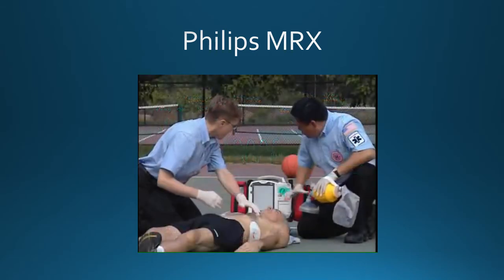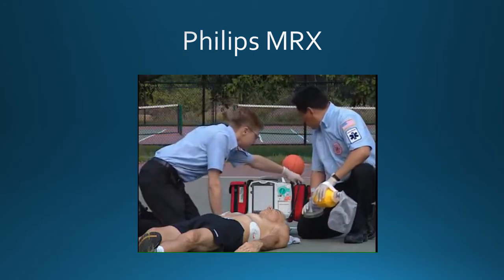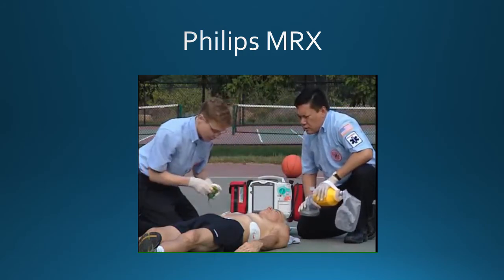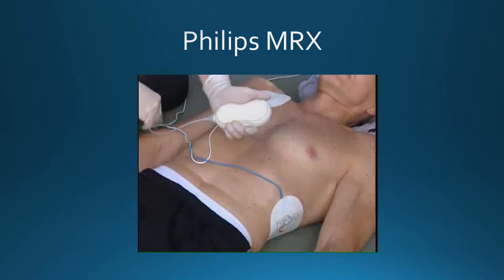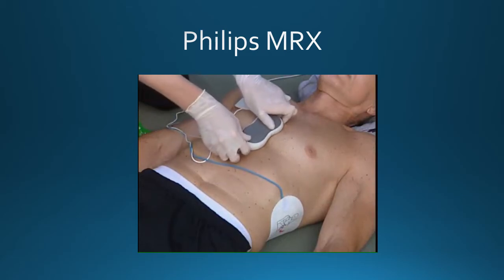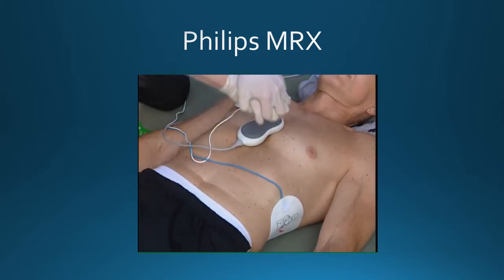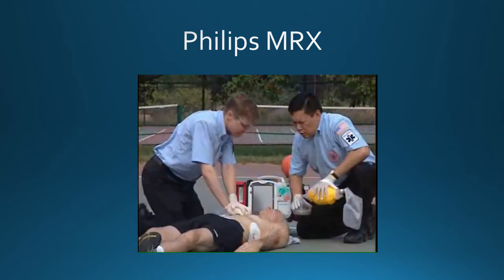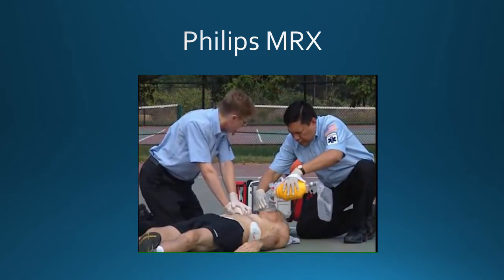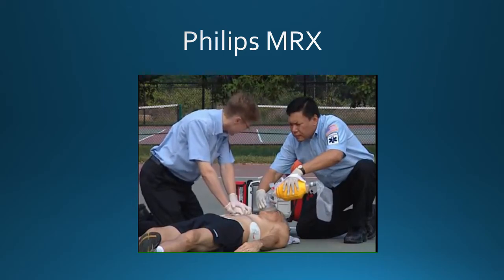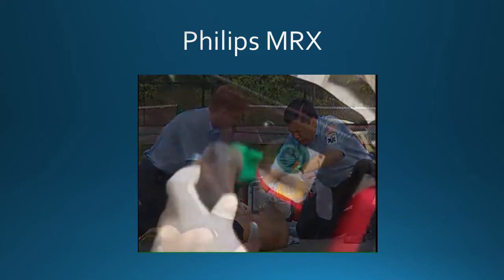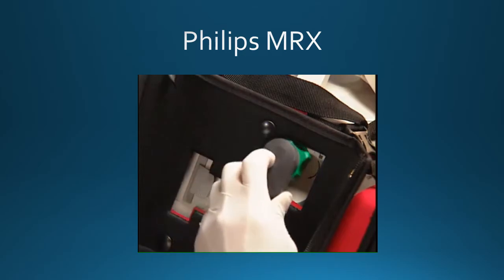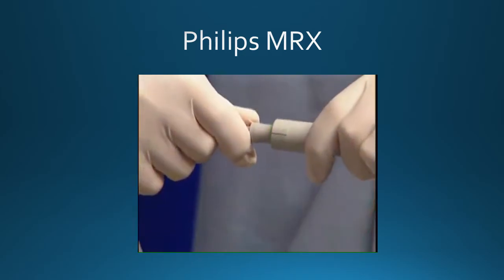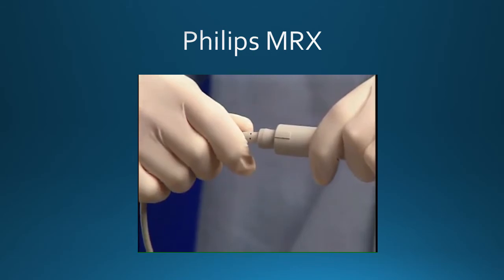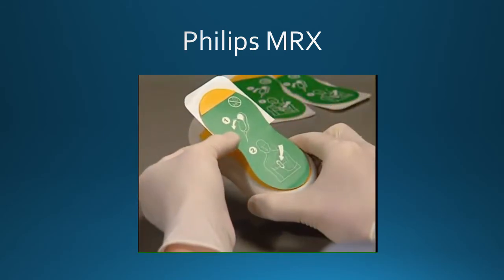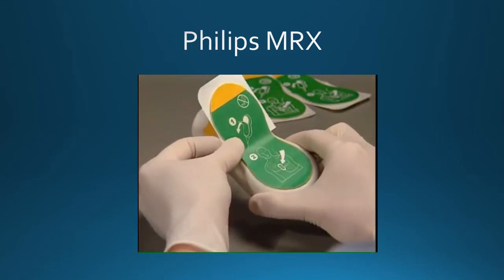It requires use of the PADS CPR cable with multifunction defib electrode pads to measure ventilations and the compression sensor to measure compressions. In this program, we're demonstrating placement of the pads first, then placement of the compression sensor. The sequence of placement may depend on the patient's condition and your particular resuscitation protocol. It is recommended that the PADS CPR cable and compression sensor cable connections and sensor adhesive pad application be made prior to patient care or emergency.